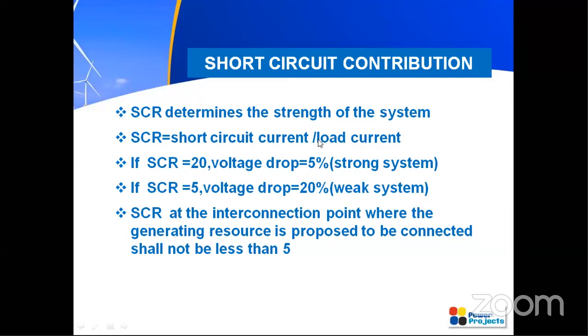You can't understand whether this is a strong system by looking at the details of this system alone, so let me take another system. Let the short circuit ratio be 5. That is, the short circuit current of the system is 5 kiloamps and the load current of the system is 1 kiloamp, so the short circuit ratio will be 5. What will be the voltage drop? It will be 20%, that is 1 by 5. It is 20%.